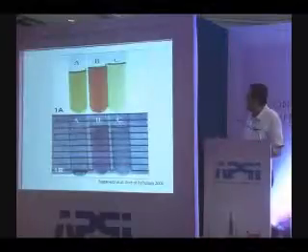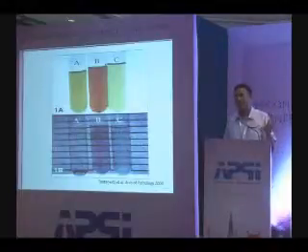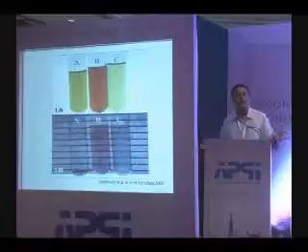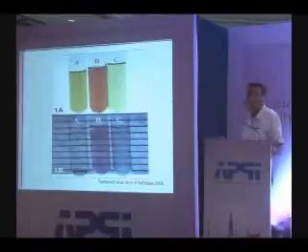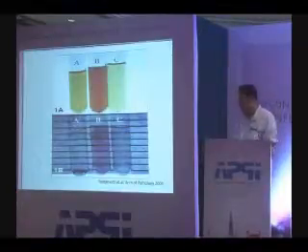What happens with a myeloma protein is that there is no color formation, but due to that precipitation effect of the monoclonal immunoglobulin, we get haziness. And again the analyzer is fooled, it reads a weird absorbance and we get a total bilirubin of 18. However, when you look at the sample, you will see that it is crystal clear.